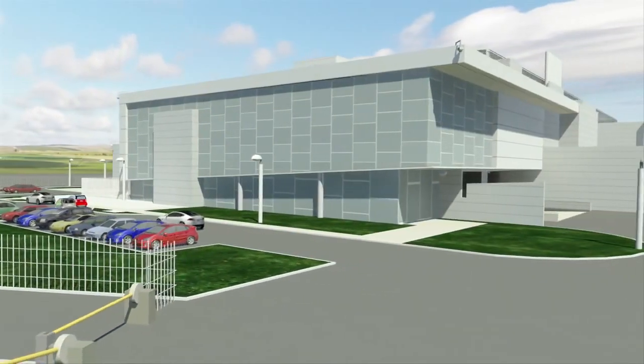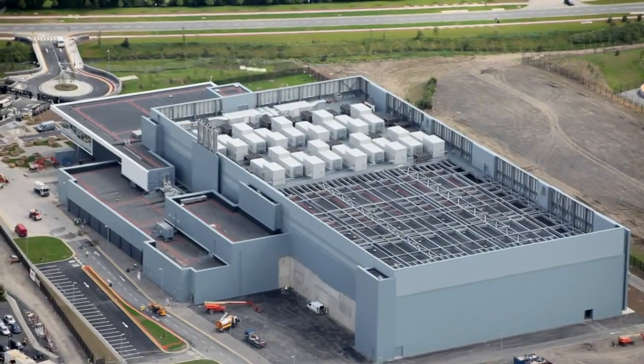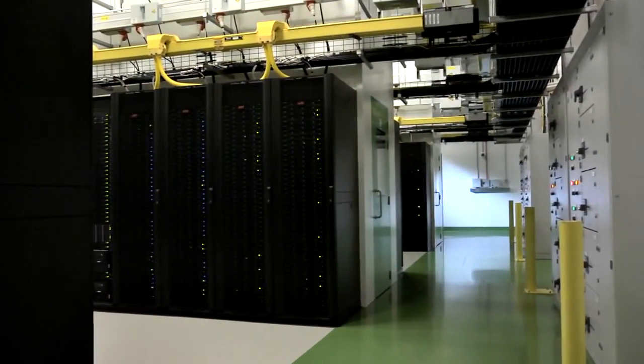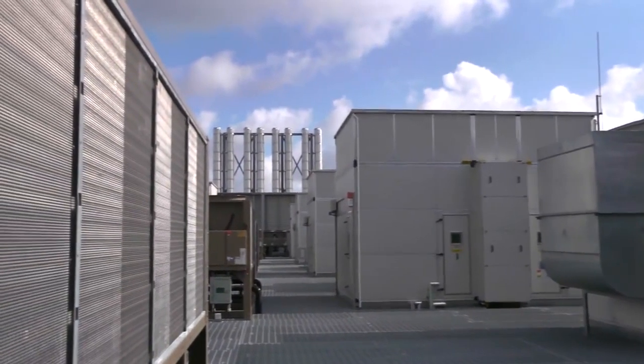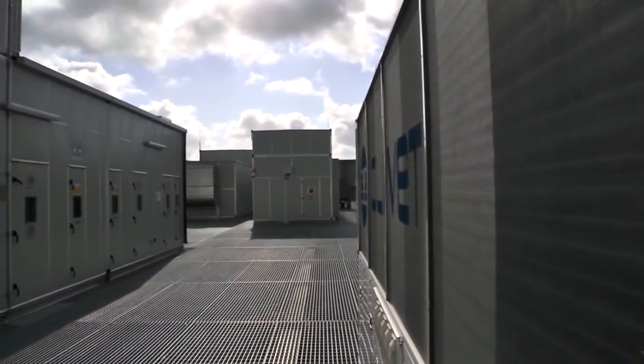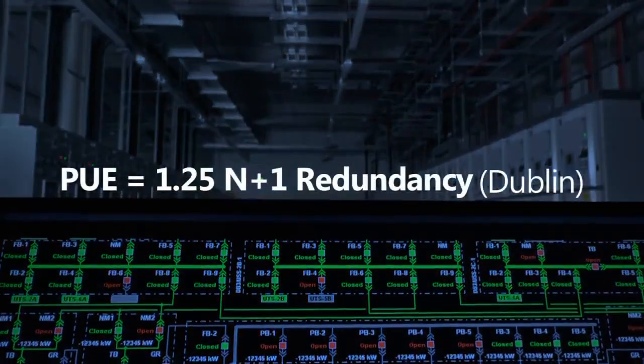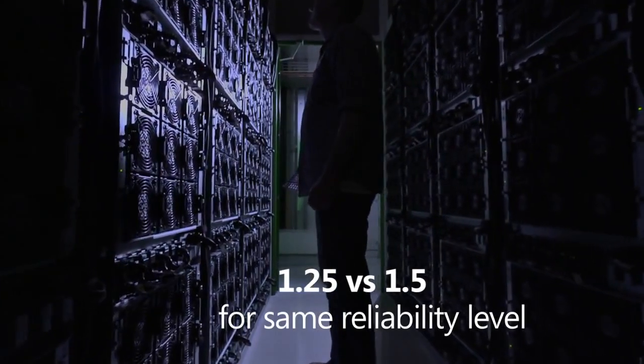Also in 2009, we further developed the containment approach to deliver additional efficiencies in our Dublin Generation 3 facility. This facility spans approximately seven football fields in size and deploys large-scale compute capacity contained in pods of servers cooled by air-side economization. Air handling units on the roof draw in cold outside air to provide cooling for the servers and facility. Evaporative coolers, vaporizing water into the air to absorb heat, and an air bypassing feature improve operational efficiency and maintain constant room temperature regardless of outdoor conditions. The facility uses less than 1% of the annual water consumption of a traditional data center, and maintains a PUE of 1.25, improving energy efficiency by approximately 50% compared to our traditional data centers of similar capacity.